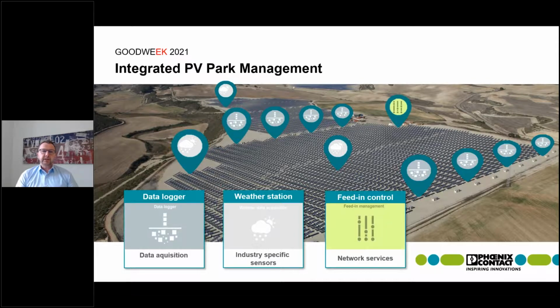Today what we're discussing is feed-in control, or feed-in management. This is only used once in a PV plant, regardless of plant size - only at the grid connection point. But this is the most complex part, because you have to handle the power at the grid connection point to feed it into the grid according to grid regulations and guidelines.